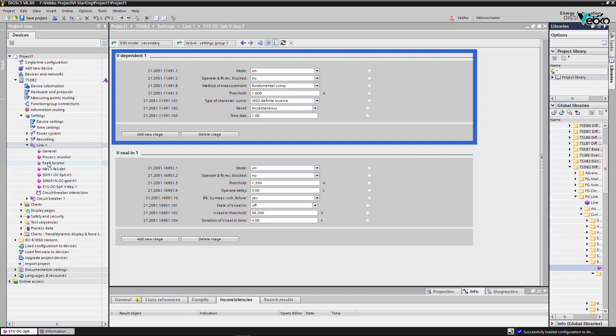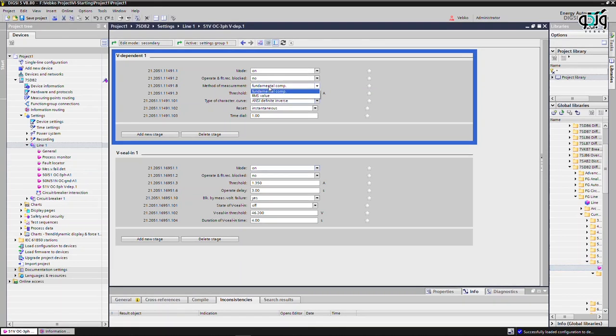The settings in the 7SD82 relay for this protection stage are performed according to the image shown. If harmonics are to be included in the measurements related to this stage, select the RMS value option in the method of measurement section. Otherwise, in order to skip harmonics and transient conditions, select fundamental component, which is Siemens's suggested option.